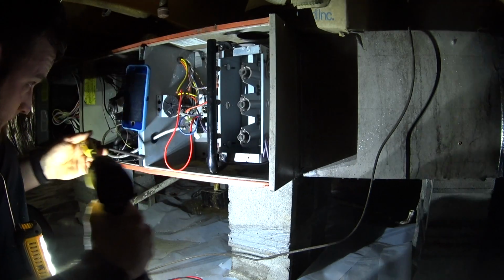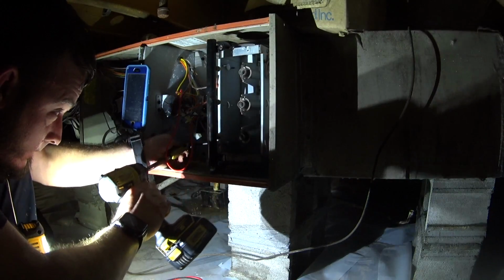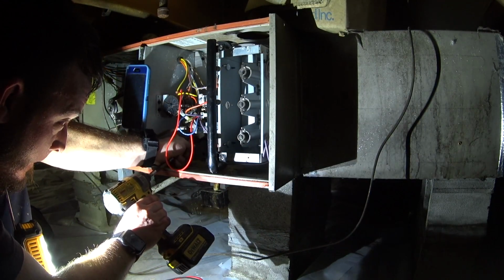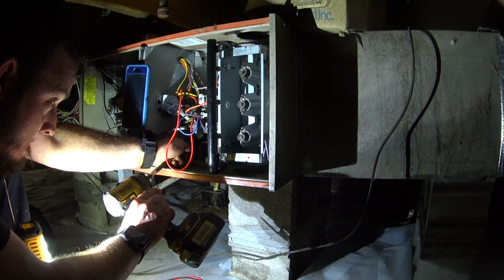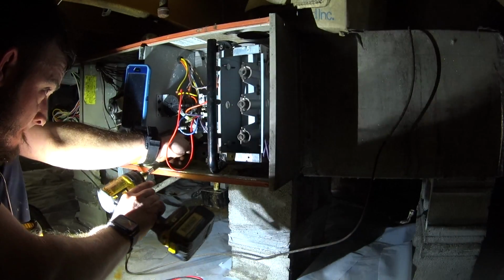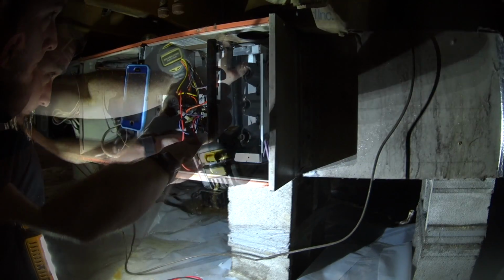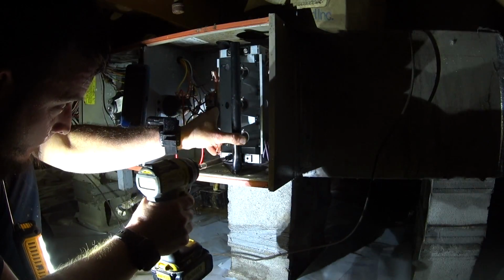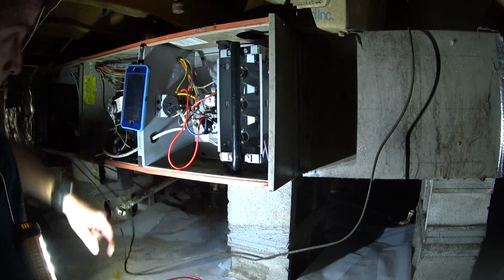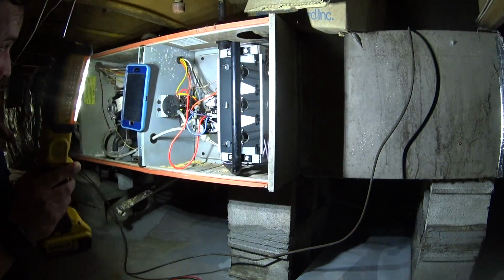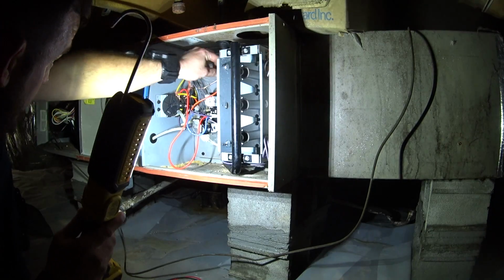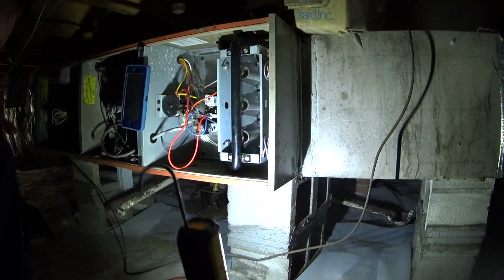Should be able to get that igniter tightened up. There we go. Okay. Burners, igniter, flame sensor, all cleaned up. I'm gonna leave the flame sensor disconnected for now. We got an ECM blower, so that's nice, convenient.